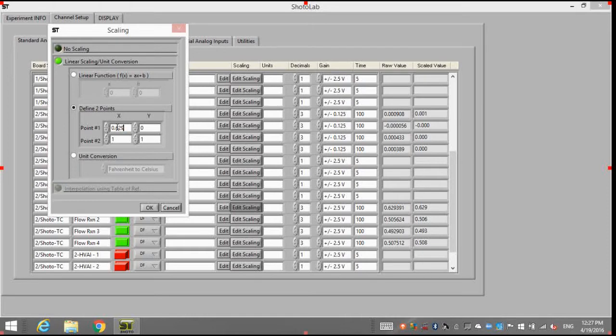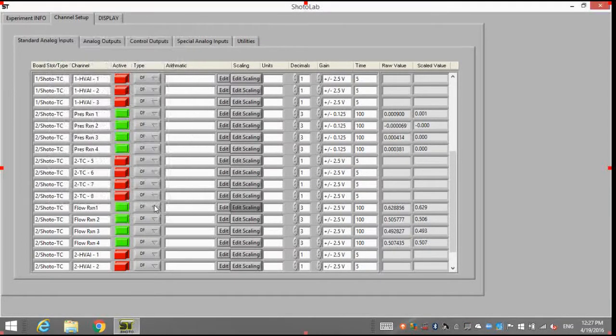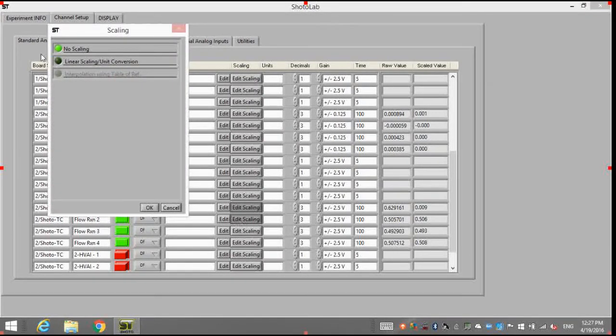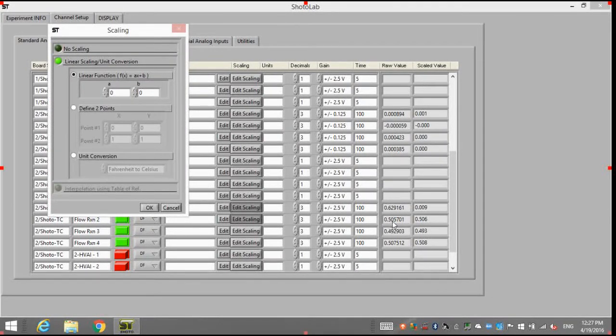To calibrate them, click the Edit Scaling. As you can see, the first flow meter is reading 0.629 at 0 flow, so let's enter that. The Y value is 2.5 volts at 100 cc, so let's enter that. And click OK. Click the second flow meter. That's reading 0.5057 at 0. Again, let's enter that and keep the 0 at 0. They read 2.5 volts at 100 cc, so let's enter that.